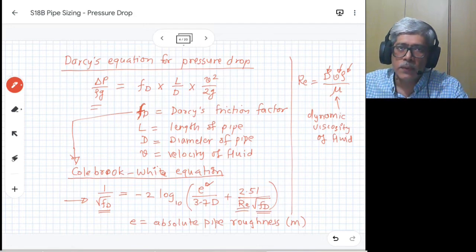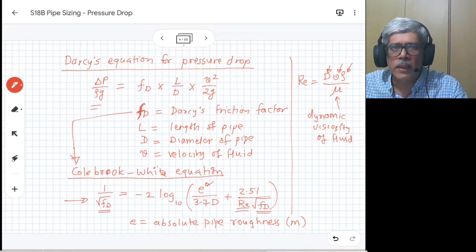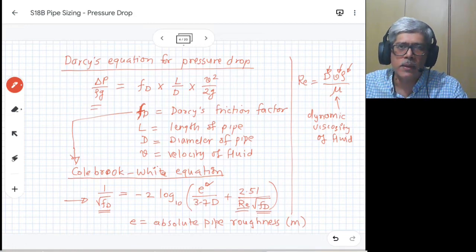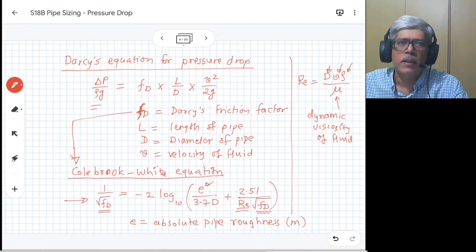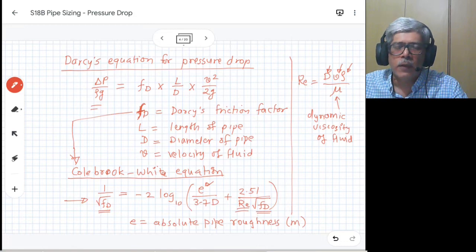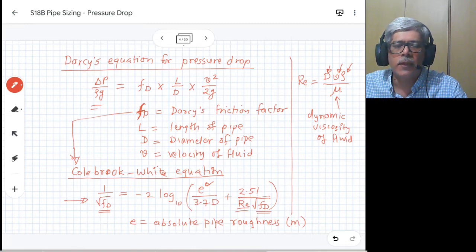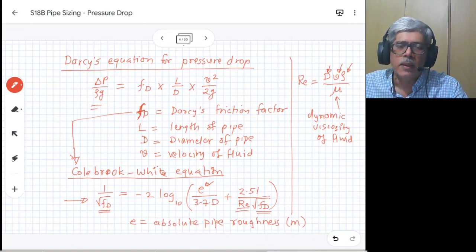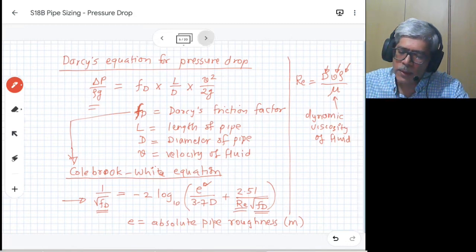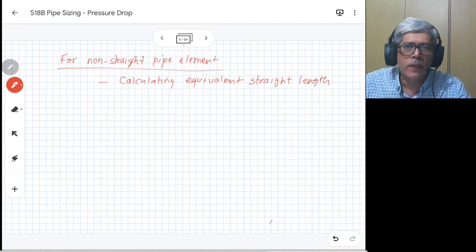As we know, the pipeline doesn't consist of straight pipe — it has got bends, T's, valves, and other obstructions or items which will increase the pressure drop. We need to account for that. One method of accounting for these different items is to convert the resistance provided by these items in terms of their equivalent straight length. So for example, if there is a valve on a two-inch pipeline, we'll convert that particular valve into an equivalent pipe of two-inch size.